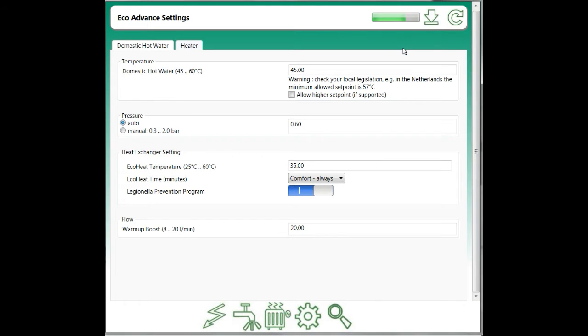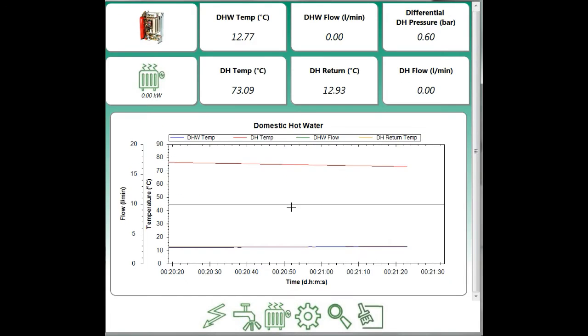We start by uploading the new settings to the data HIU. Domestic hot water is at 45 degrees C. We have the keep warm temperature at 35 degrees C. Switching to the output view, we can see the data coming out of the HIU.